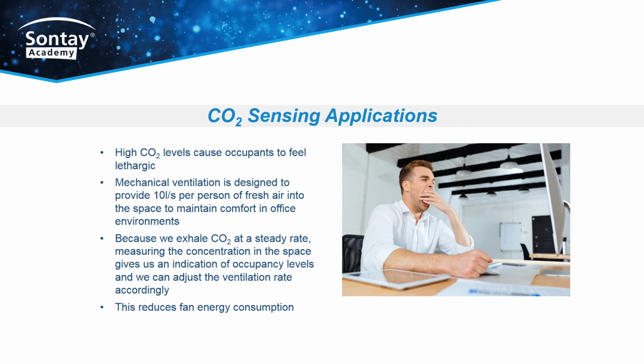Demand-controlled ventilation requires a measurement of anything which gives an indication of the number of occupants within a space. Because we exhale CO2 at a constant metabolic rate, we can use the concentration of CO2 in the space to give an indication of the number of people in a space, and therefore how much fresh air needs to be provided. Higher concentrations of CO2 indicate higher occupancy, requiring additional fresh air delivery, and conversely lower CO2 levels indicate that less fresh air is required to meet the needs of the occupants.